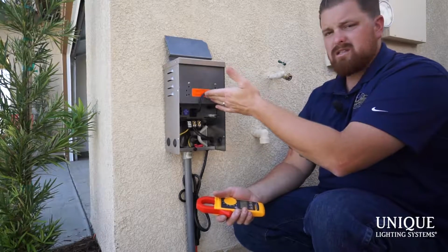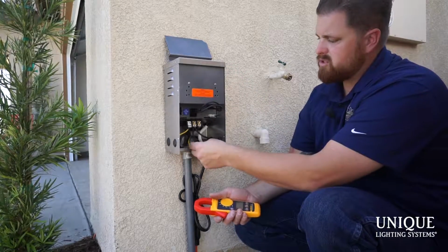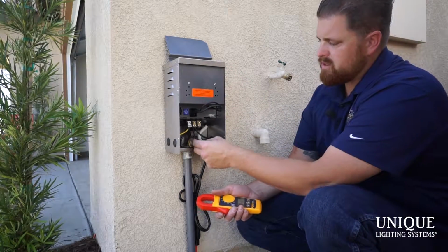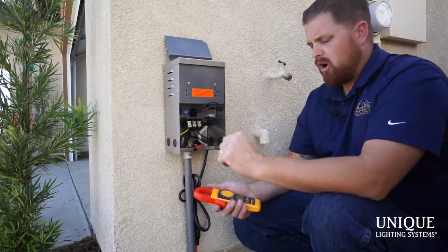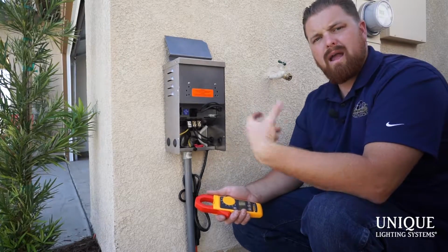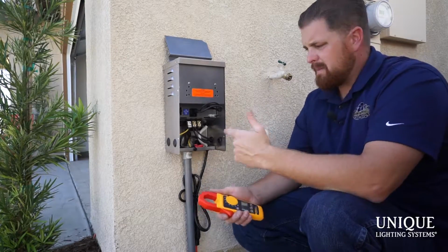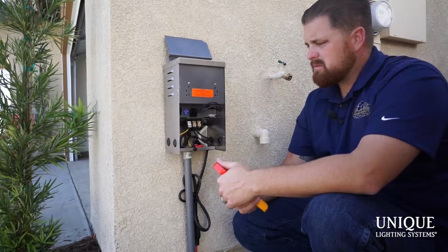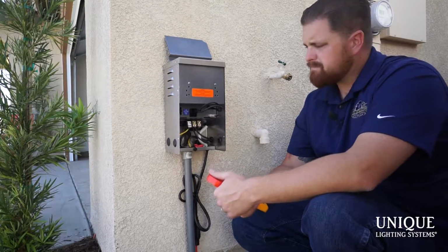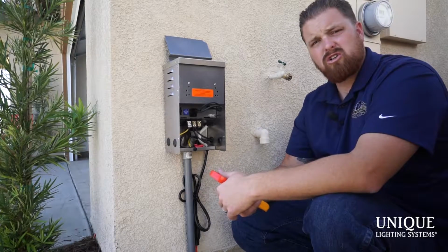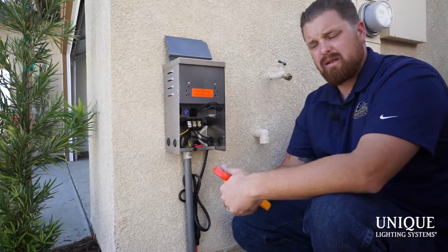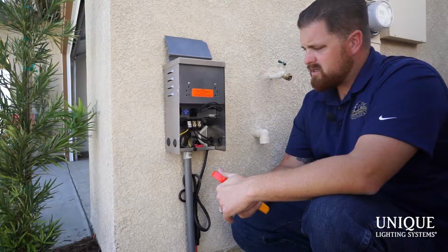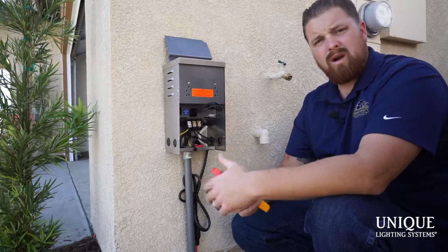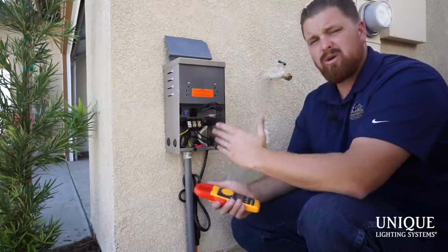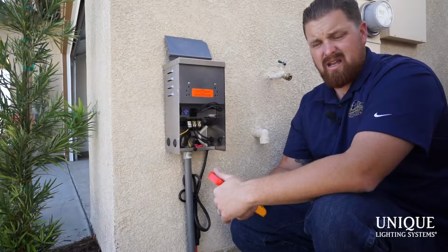So now primary is the 120 volt side, secondary the low voltage side, and so what I'm going to check for is I'm going to make sure that none of my home runs are going to be over the maximum allowable amps for the size wire they are. These happen to be 12 gauge wires, so maximum amperage is 20 amps. Now, generally the National Electric Code is going to tell you that you can't exceed 80% capacity on these wires. So 80% of 20 is 16 amps. So my maximum amperage I want to check for is nothing over 16 amps.